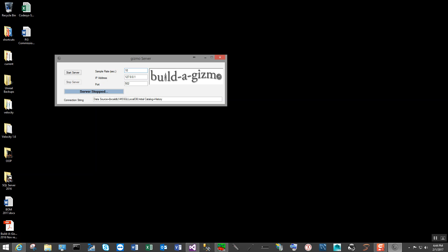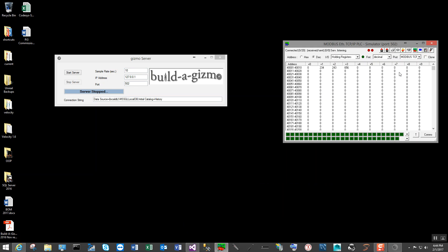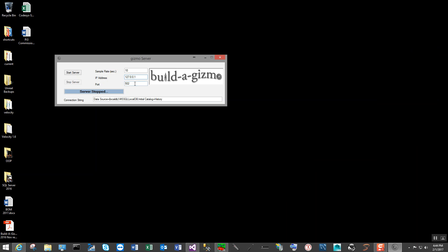These are all standard devices. Modbus TCP is a standard protocol. SQL Server from Microsoft is the de facto standard in the industry. I'll change the sample rate to 10 seconds, and the IP address in this case is my local host, which is what is being run in this simulator — running on the local host and listening at the local host level. The port is 502, which is the standard TCP port.